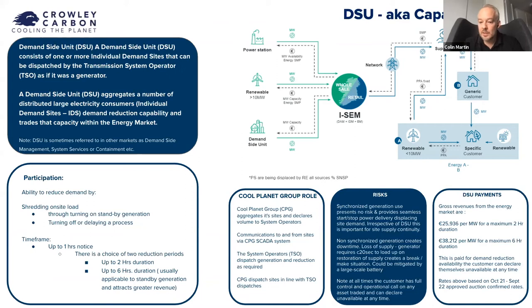This could be a diesel generator, turning off a heat pump, or a combination of a battery, a heat pump, and a diesel generator—whatever it is, you have to make that 1 megawatt available. If you make it available for either 2 hours or 6 hours when called upon, you can collect between 26,000 and 40,000 euros per annum per megawatt. If you make it available, even if it's not called upon, you'll still get that money. When it is called upon, it needs to be provided, and that's the key to maximizing those revenues.